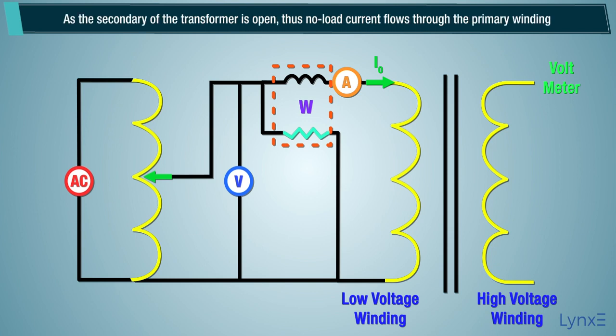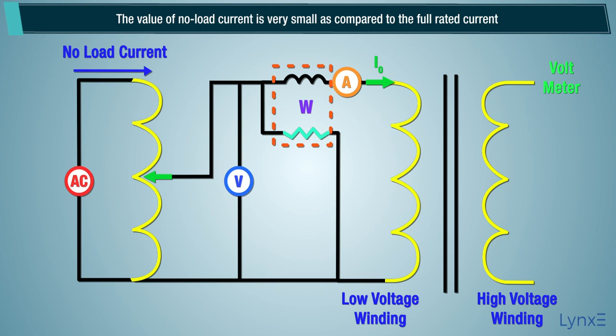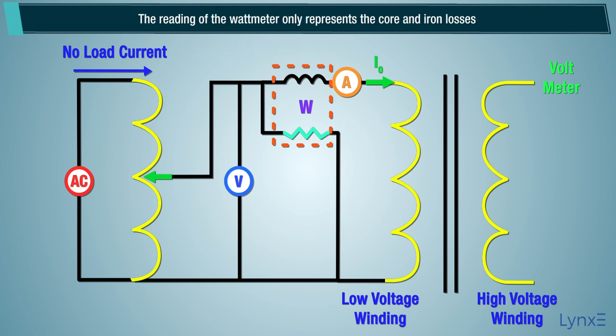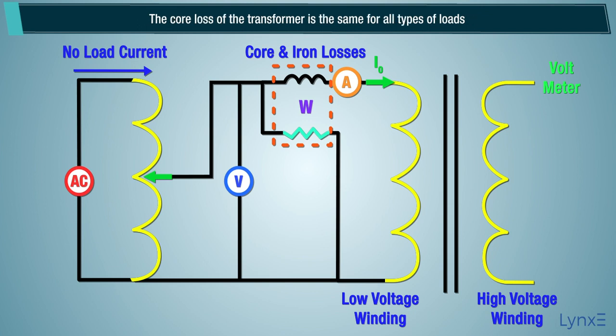As the secondary of the transformer is open, no-load current flows through the primary winding. The value of no-load current is very small as compared to the full rated current. The copper loss occurs only on the primary winding of the transformer because the secondary winding is open. The reading of the wattmeter only represents the core and iron losses. The core loss of the transformer is the same for all types of loads.